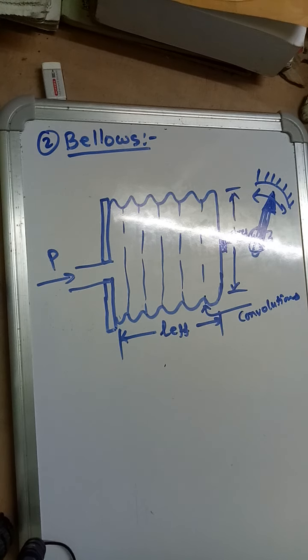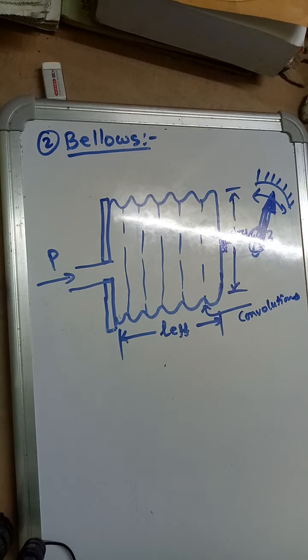The bellows element is basically a one-piece expansible, compressible, collapsible, axially flexible member. It consists of several convolutions or foldings. It is usually formed in one continuous operation from a thin seamless tube into a deeply folded or corrugated unit by either a hydraulic or mechanical method. It may be made from a continuous piece of thin metals.